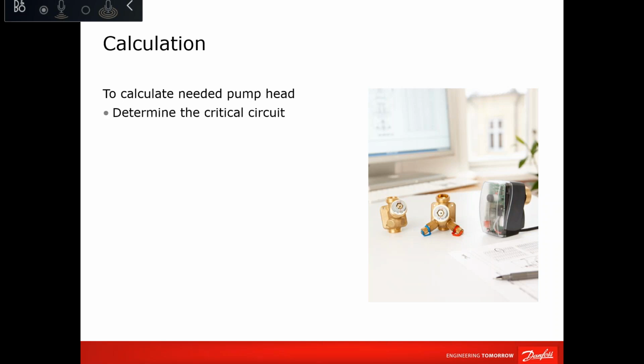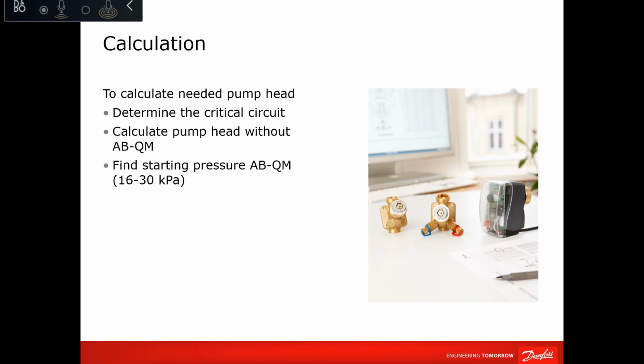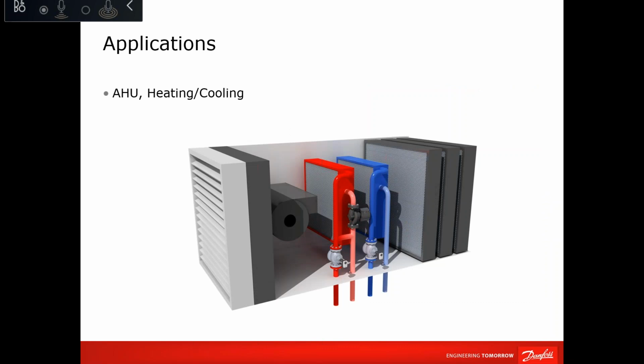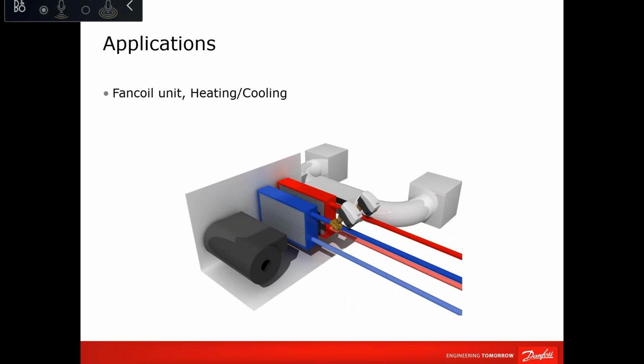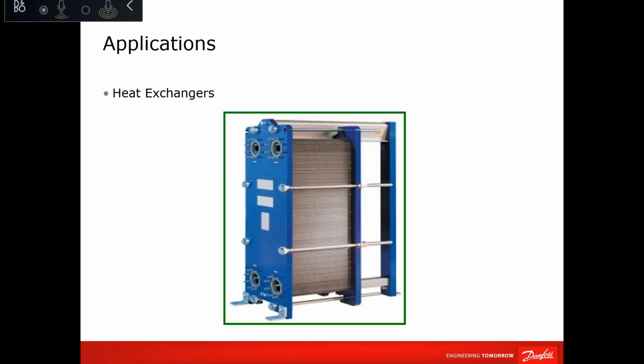But in case you are doing it, just determine the critical unit, calculate the pump head without the valve, then add the static pressure of the PICV, which is between 16 to 30 kPa. Application: air handling unit, fan coil unit, heat exchanger, most known application.